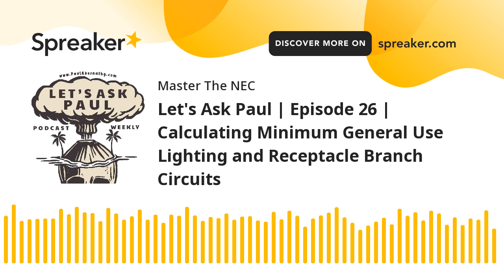So let's say we have a one-family dwelling. And of course, we know that in 220.12(J), and you're in the 2020 edition of the National Electrical Code, so you can always pause this podcast, go grab your code books, go to 220.12 and you'll notice J. J will tell you that it's 3 VA per square foot. Now, it used to be in the 2017 edition, that was up in 220.12, and it wasn't down in J. You basically would look at the table at 220.12, and that's where you'd see dwelling units, and that's where you get the 3 VA per square foot. So that has changed for the 2020 edition.